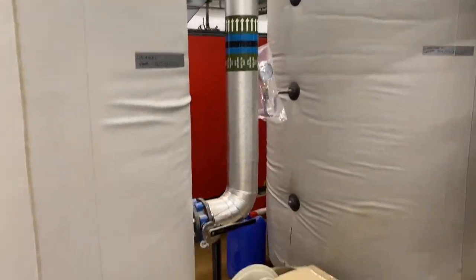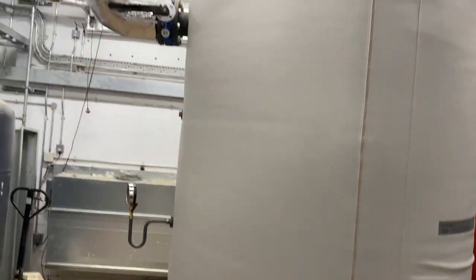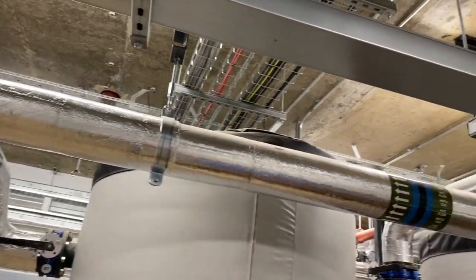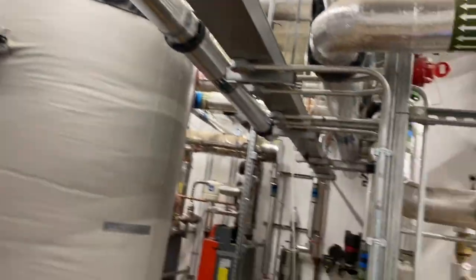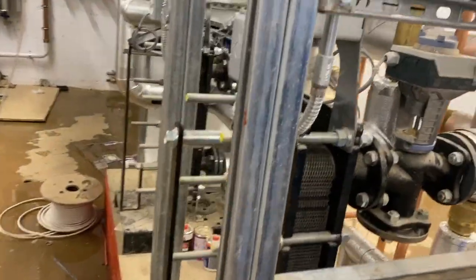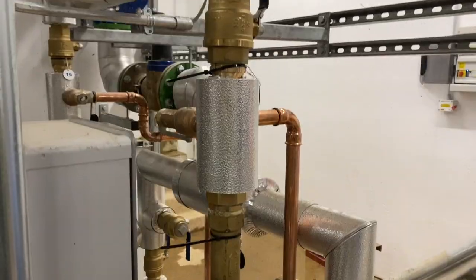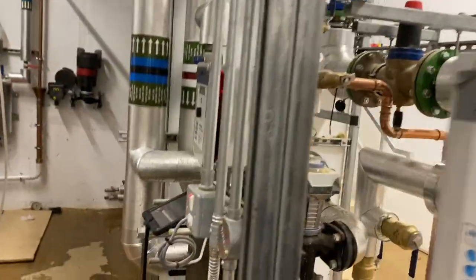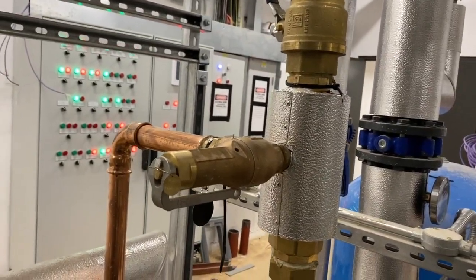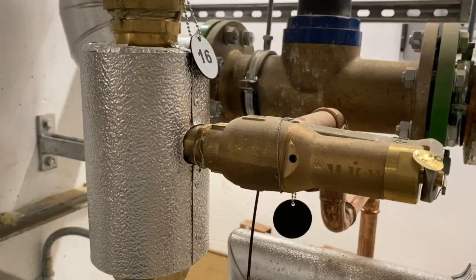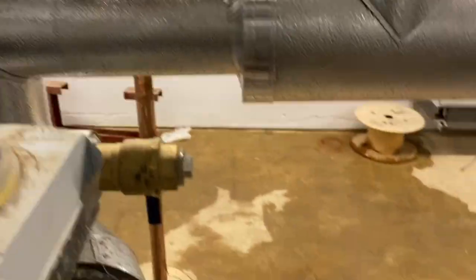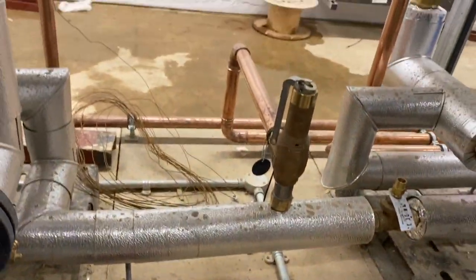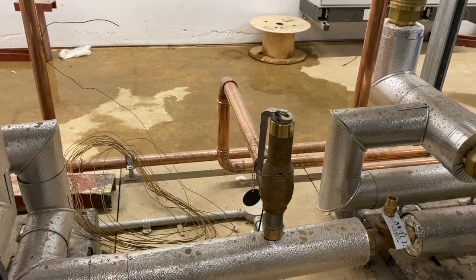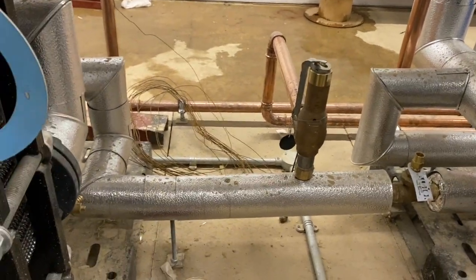These are actually buffer vessels on the heating side. So these are what is loading the plant via the boilers. Over the back there. Make sure 6-bar pressure relief valve. Any isolation valves still need to have another 6-bar relief valve. Make sure no one can cut off the safety devices.